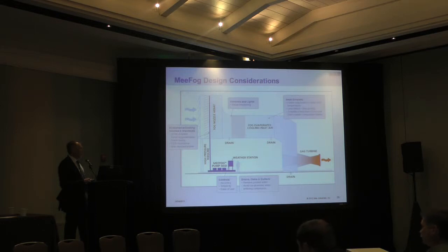And we do that because it's hard to get sensors that are accurate close to the turbine inlet. They're adversely affected by the high airflow, particularly humidity sensors. They can get wet from liquid water that's in the vicinity, and so they read too high, etc. So that's how we do it. We calculate how much water is needed, and we inject that much water.